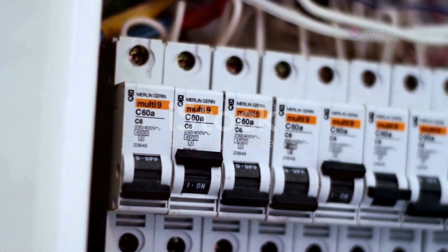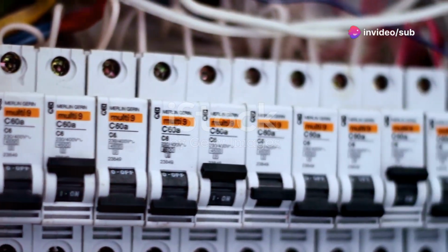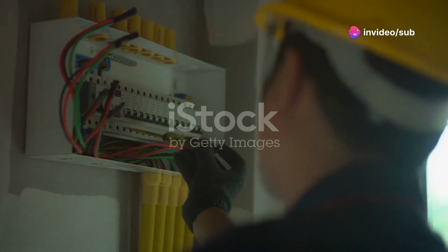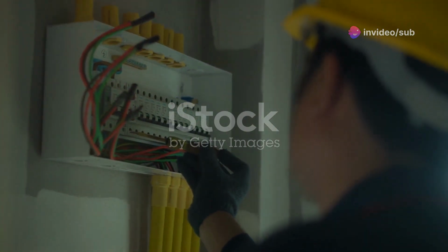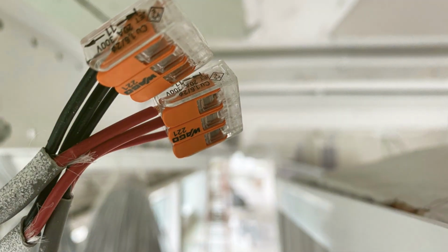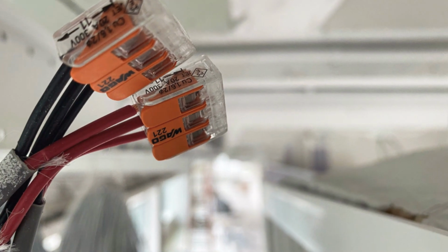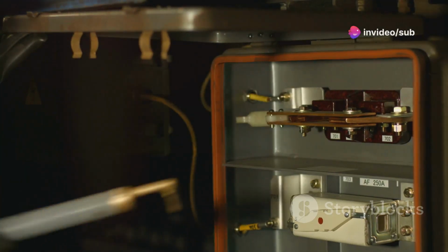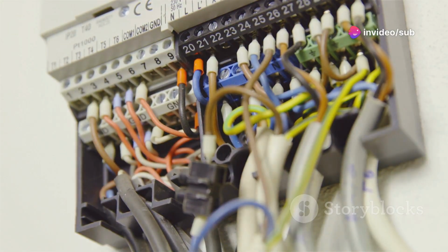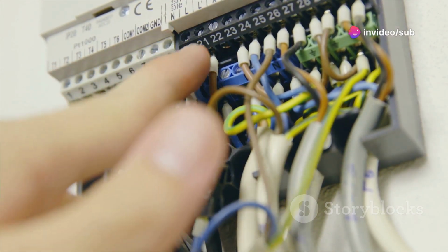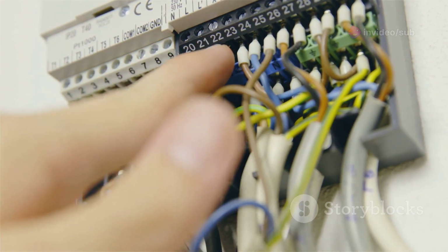When people spot breakers with more than one terminal, the questions really start rolling in. Are these terminals interchangeable? Can you split the wiring between them, or are they for a special purpose only? Is connecting more than one wire to the same terminal a shortcut or a mistake? These questions are genuinely important. Using the wrong terminal or connecting wires incorrectly could definitely lead to problems down the road.